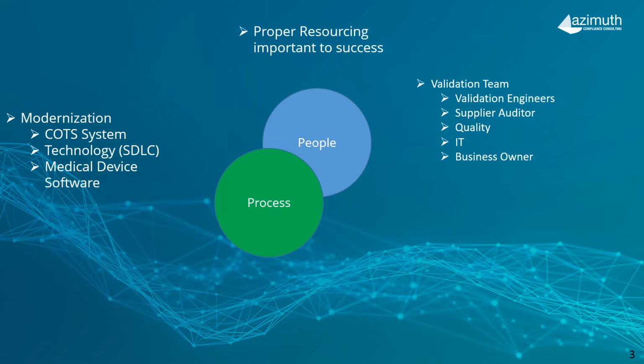Build quality into the process by combining the development and validation as one and the same, not as a separate piece of the project. Take advantage of the testing performed by the development team to ensure that those items typically tested in OQ are included as part of the software testing. An example would be verification of calculation, the upper or lower limits of valid fields, or values of fields, or if fields are required or not.